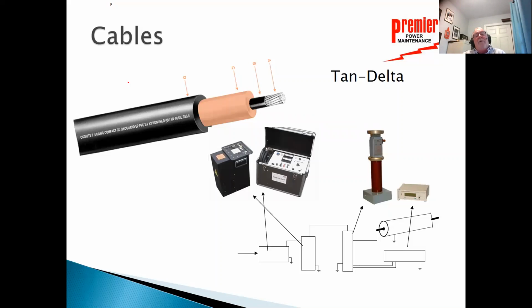Now, unfortunately for cable testing, it has to be taken out of service, but there are so many new test techniques. One of them is a tan delta, where, if I closely monitor while I'm testing, I can look at what it used to be when it was brand new and compare what the condition is now. And I can ramp up the voltage, and I can actually shut the test set off if there's any indication that that cable could fail during the test. Very, very solid test. So when cables get to a certain age, we need to be testing those cables to see what kind of life is left. And that tan delta test is one that can really assist us in determining that.